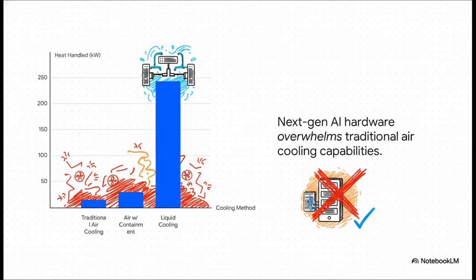This chart shows you exactly why the old ways just don't work anymore. A standard server rack cooled by air can handle maybe 15 kilowatts of heat. If you get really fancy with containment, you can push it to 30. But the next generation of AI hardware, we're talking 200 kilowatts or more per rack. Air cooling doesn't just struggle at that point, it's physically impossible. It just can't keep up.